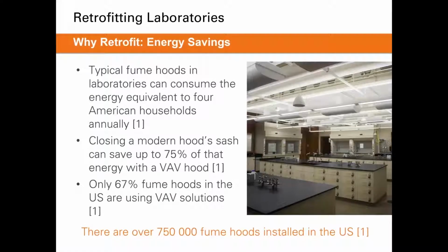The third point here, only 67% of fume hoods in the US are using VAV solutions. And I put in that number again at the bottom there. There are over 750,000 fume hoods installed across the US. And if only 33% of those fume hoods are using a constant volume solution, and if 75% of that energy can be recovered back by switching to a VAV solution, then that just shows you that there's an enormous opportunity across the US for significant energy savings, and that can be accomplished by going back and seeing what hoods can be replaced in existing labs and doing these retrofit projects.